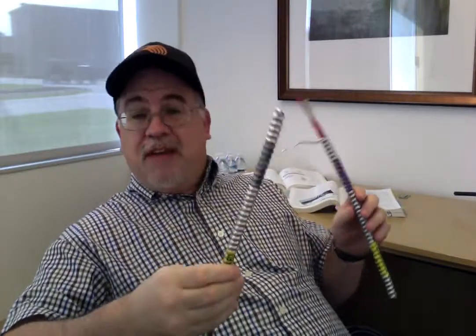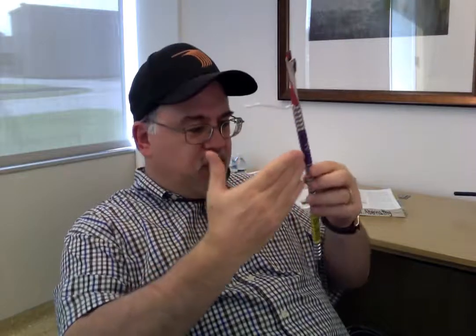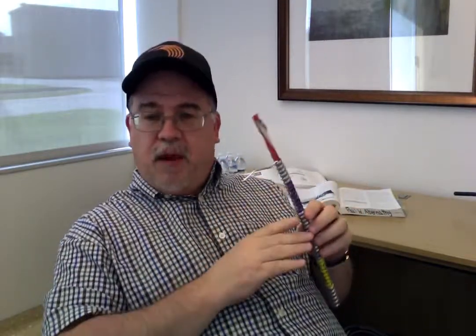What does that mean for you in the world of using this product? Well, this is a labor savings product. Under the normal MC, you have to terminate that equipment ground at every termination. Under the SmartGround product, you don't have to do that, because you have this 10 gauge aluminum grounding/bonding conductor that, once it's installed and it touches all of the convolutions in this armor, is considered an effective ground fault current path. And where does it say that in the standard?